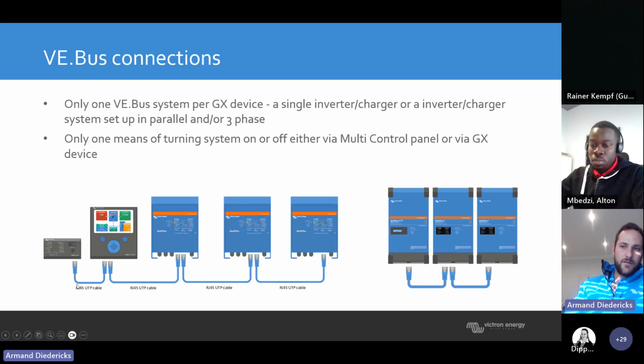Ensure if you don't have a digital display connected to the output that you install a dummy plug - you get it with the GX or all the GX devices. It acts as a terminator, so terminate the ends, otherwise you're going to create an open loop. Terminate this side and terminate the other end of the inverter to ensure there's proper communication going through.